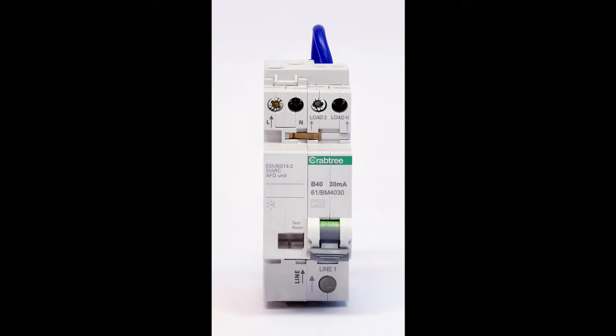Starbreaker consumer units use an innovative instant self-connection system by employing a unique busbar system that devices simply plug into for instant push-fit connections that give guaranteed factory-quality connections. This makes the installation of devices easier, safer and faster. AFDDs can be simply plugged into the fully insulated plug-in busbar system for an easy installation that meets 18th edition standards for additional protection against electrically ignited fires.